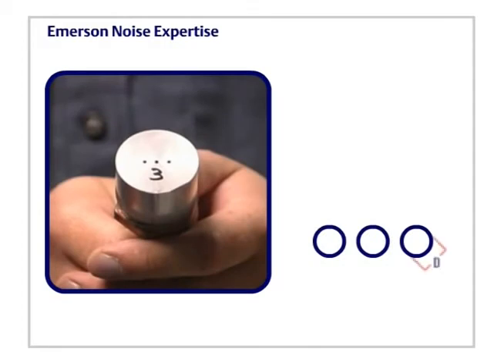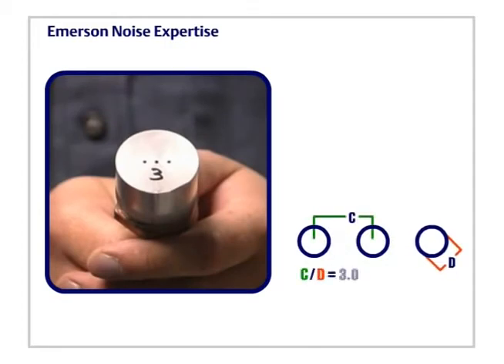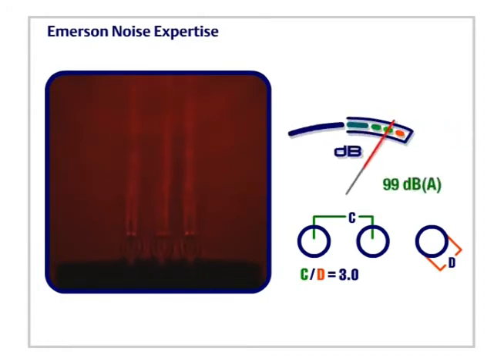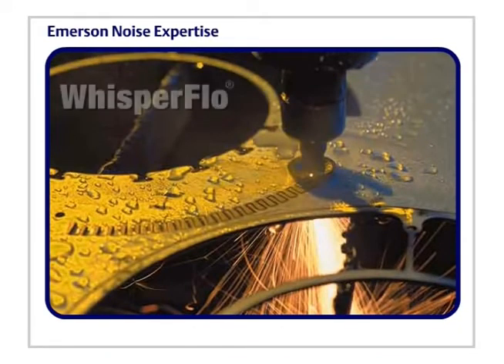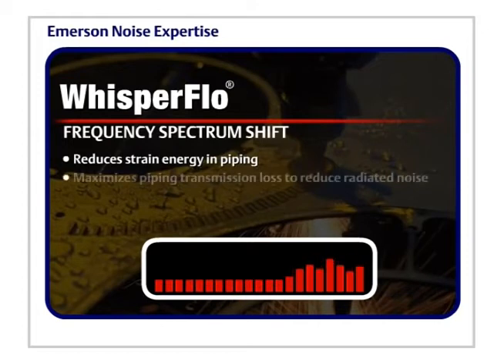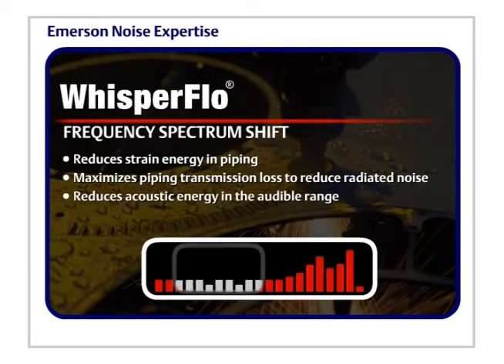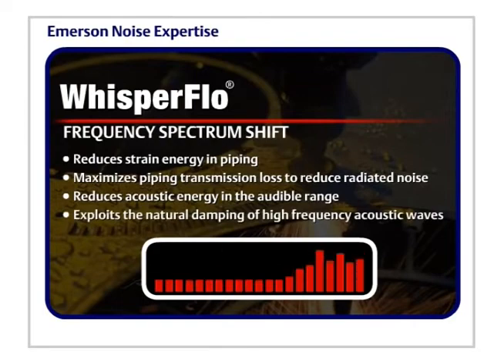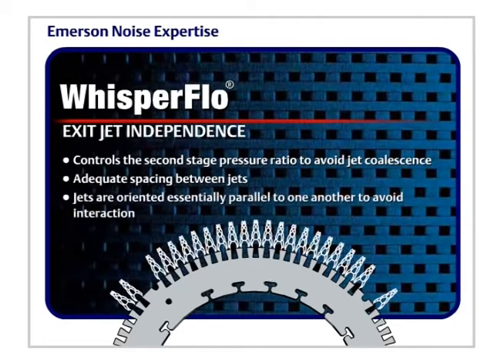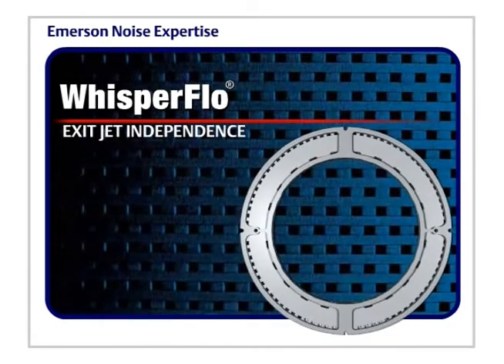This example uses the same three holes, each one-eighth inch in diameter, but the spacing ratio is three — in other words, the distance between the holes has doubled. This time, the jets stay independent for the duration of the test. Emerson's noise reduction expertise helps produce products like WhisperFlo, which incorporates Fisher's noise reduction technology. WhisperFlo trim features frequency spectrum shift, reduces strain energy in piping, maximizes piping transmission loss to reduce radiated noise, reduces acoustic energy in the audible range, exploits the natural damping of high-frequency acoustic waves, exit jet independence, controls the second-stage pressure ratio to avoid jet coalescence, and maintains adequate spacing between jets. Jets are oriented essentially parallel to one another to avoid interaction.